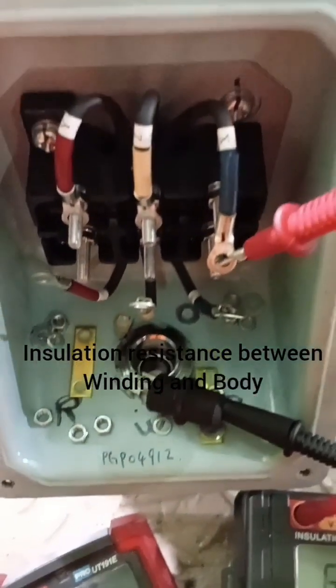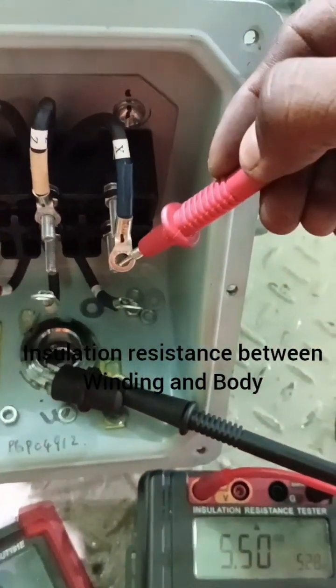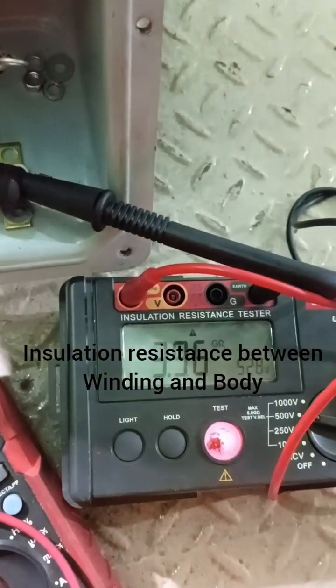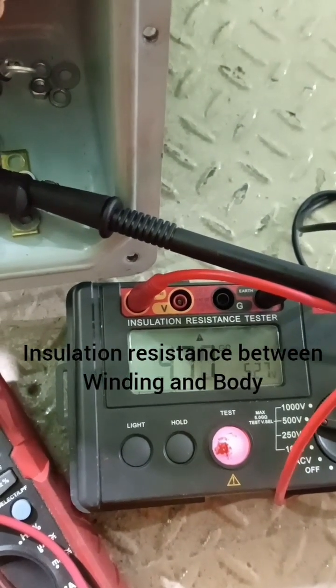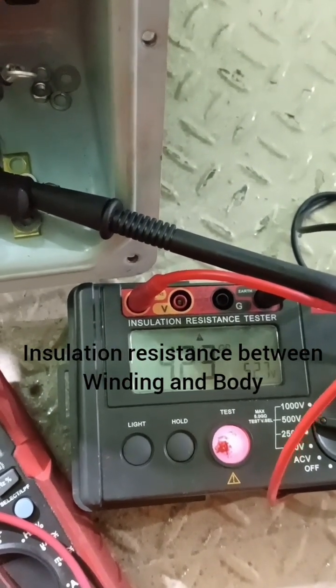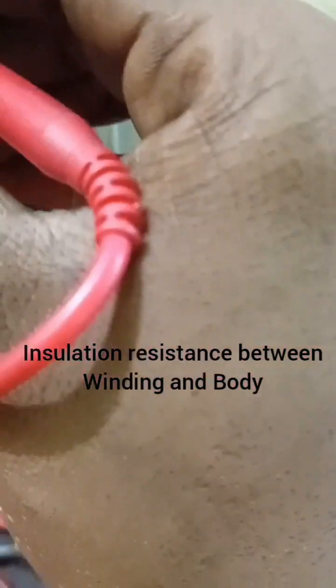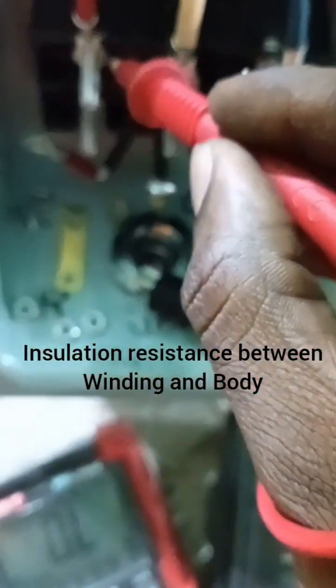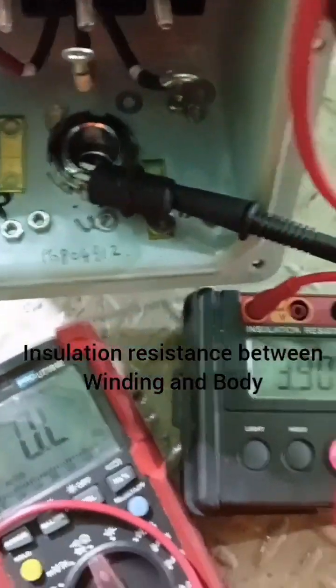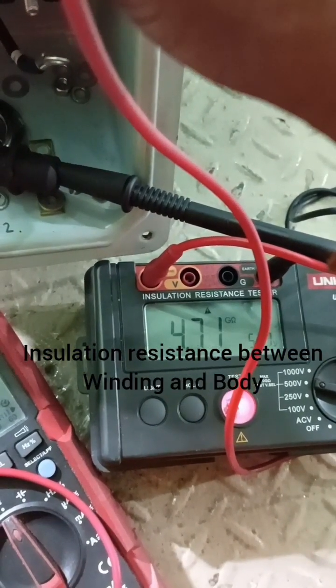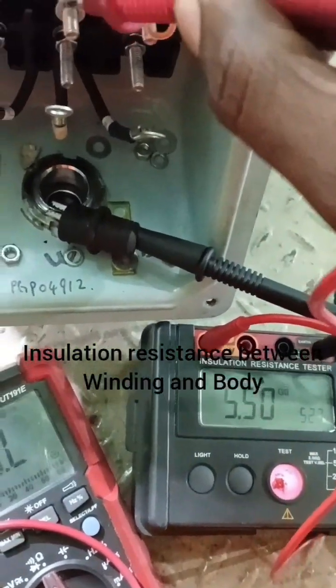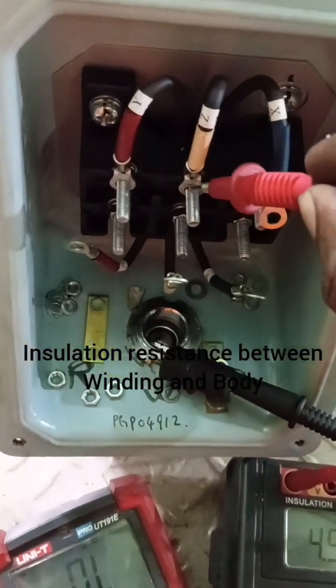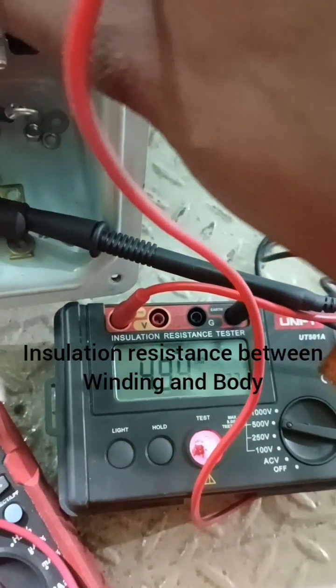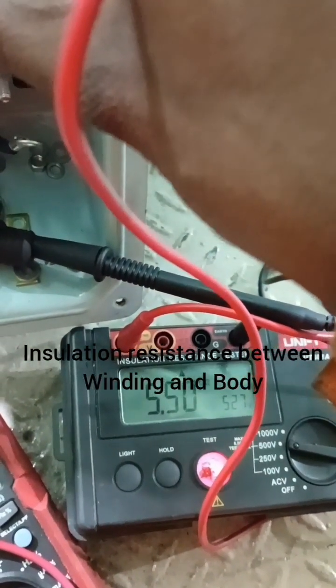So we came to know that the motor windings are not shorted. I am measuring the insulation resistance between the body and X1. It was around 5 megaohms. The insulation is in good condition, so we need not put any additional varnish. We can assemble it as it is. All windings are giving around 5.5 megaohms.